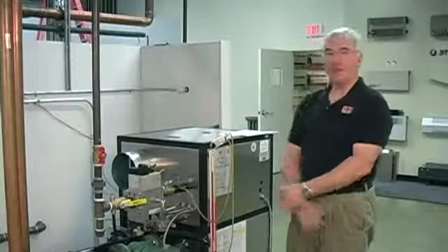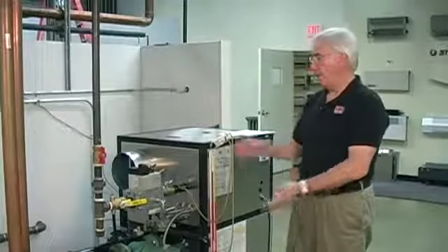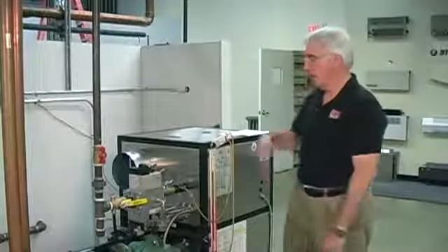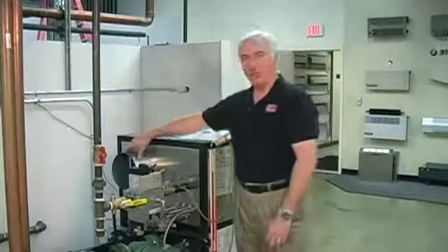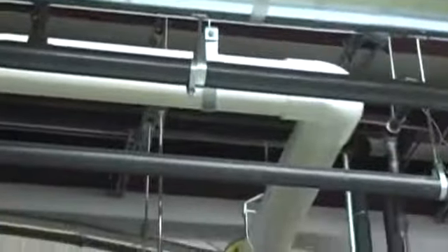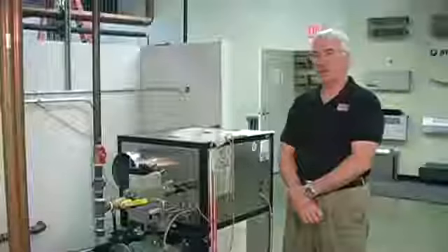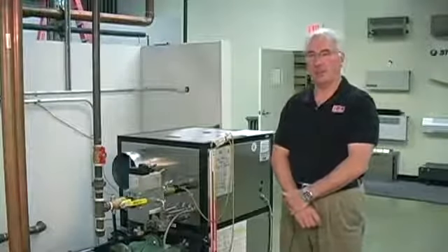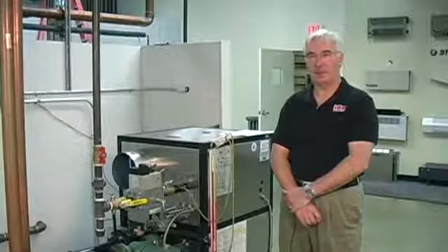In this particular environment here, we have the boiler taking room air. If you actually happen to be taking air from outside, the air inlet cone would be attached to a piping system that goes out to the outside air. Now, if you're in a particularly cold part of the country, you have to be aware that the cold temperatures are going to have some impact on combustion. The colder the air, the denser the air, and the denser the air, the more oxygen there is in the air coming into the unit.